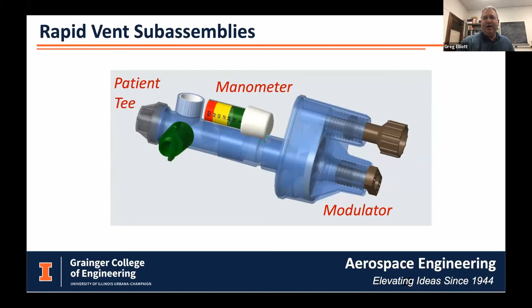The patient T assembly first provides a connection so that we can hook up the tubes that go to the patient. There's the breathing tube that connects to the patient. We also incorporated a safety feature, as the reference design did too. This is a one-way flapper valve. We designed a valve that would open if the patient, sometimes, whenever they use these respirators, quite often the patient is put under anesthesia, and so this device is breathing for them. But every once in a while, if they wake up, they would take a breath themselves, and so that would not damage the device or damage their lungs.